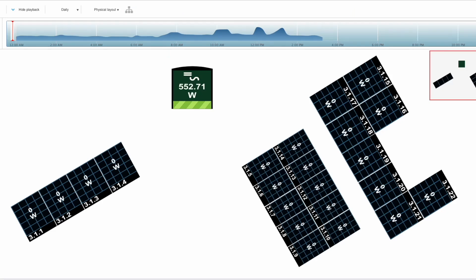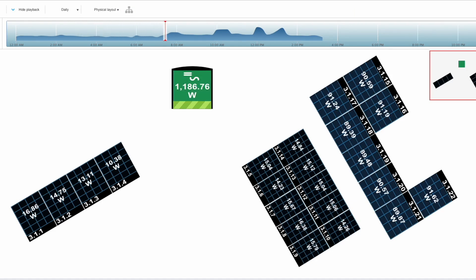I'm going to bring up an animation that shows each panel — it's going to take a day from about six o'clock in the morning through to about four o'clock in the afternoon. You'll see that those north-northeast-facing panels start to generate about two and a half hours before the panels on the south-southwest or south-southeast parts of the roofs. The panels on the right-hand side of the image, on the north-northeast-facing roof, start generating at about 6:30 in the morning, and they build up a couple of kilowatts of power before the panels on the south side even start to generate anything.